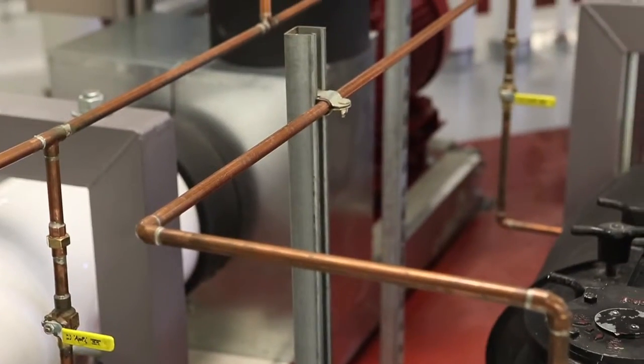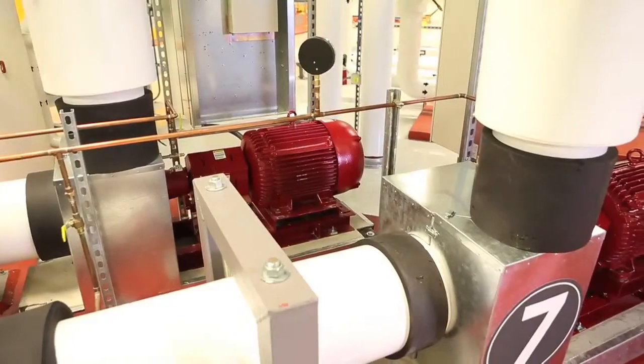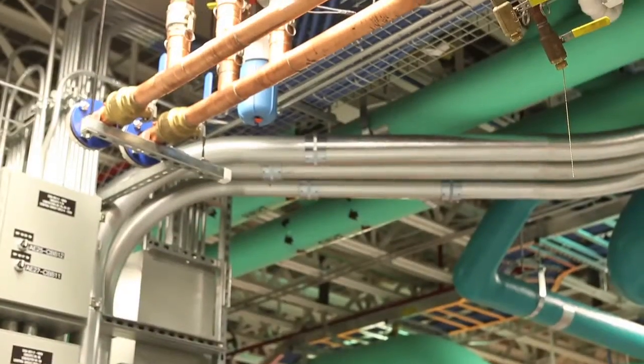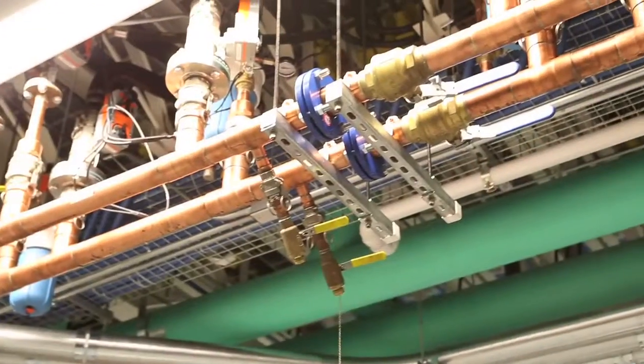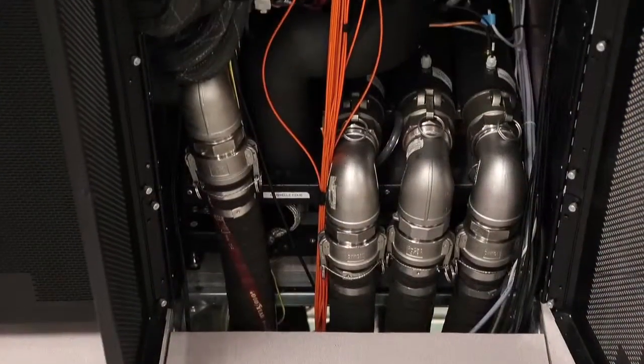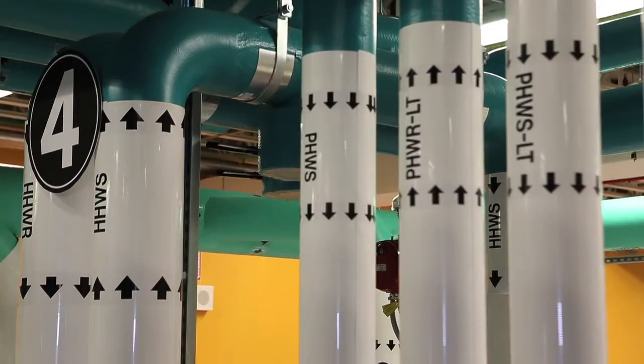High-performance computing data centers, which is what we do here, have a very high energy density per rack, about 70 kilowatts per rack. When you get to those high densities, you can't cool them with air anymore, but we can take warm cooling water, 75 degrees or so, run it up to the rack, and then come back with 95 or 100 degree water. We can take that warm water and then do other useful things with it.